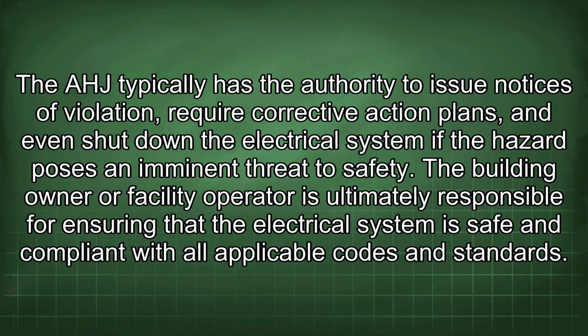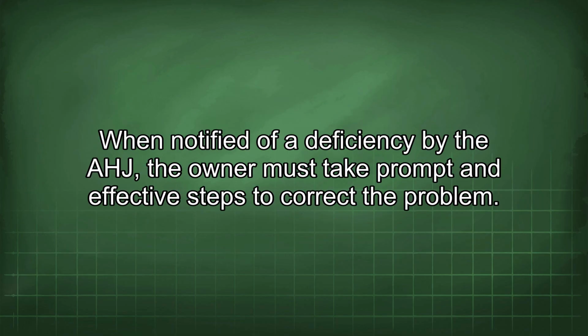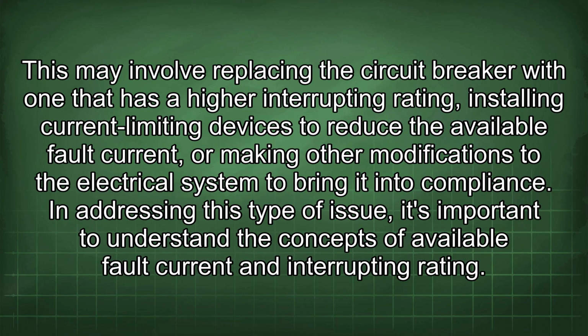The building owner or facility operator is ultimately responsible for ensuring that the electrical system is safe and compliant with all applicable codes and standards. When notified of a deficiency by the AHJ, the owner must take prompt and effective steps to correct the problem. This may involve replacing the circuit breaker with one that has a higher interrupting rating, installing current limiting devices to reduce the available fault current, or making other modifications to the electrical system to bring it into compliance.